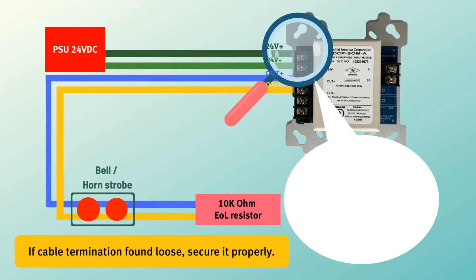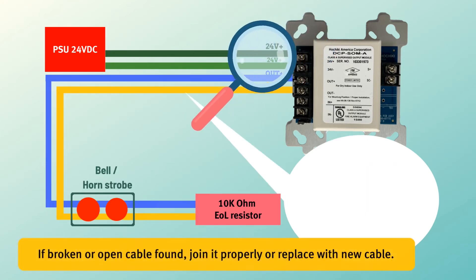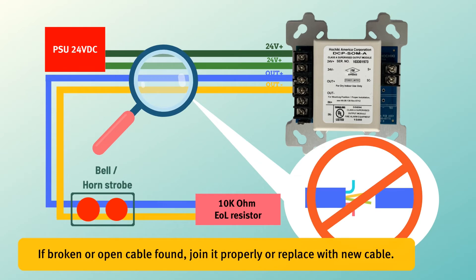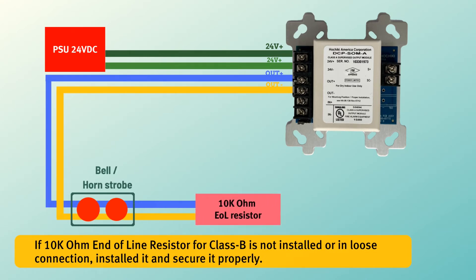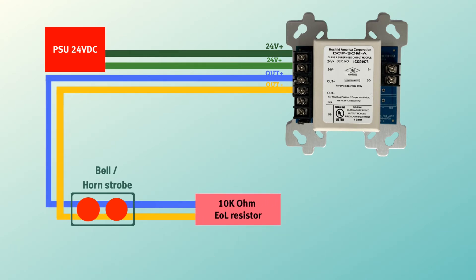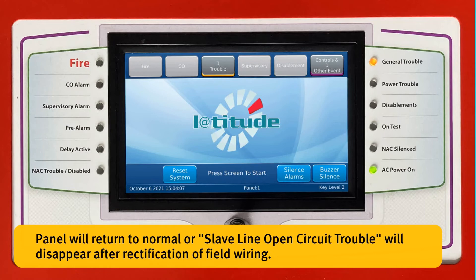If a cable termination is found loose, secure it properly. If a broken or open cable is found, join it properly or replace it with a new cable. If the 10k ohm end of line resistor for Class B is not installed or has a loose connection, install it and secure it properly. The panel will return to normal and the slave line open circuit trouble will disappear after rectification of the field wiring.